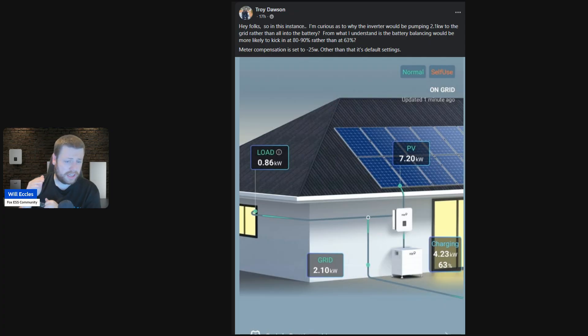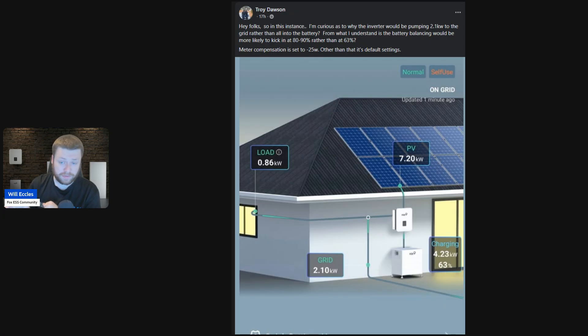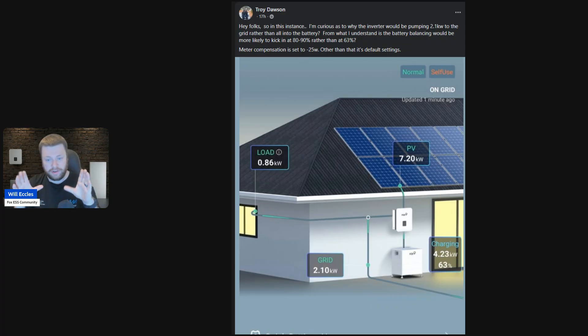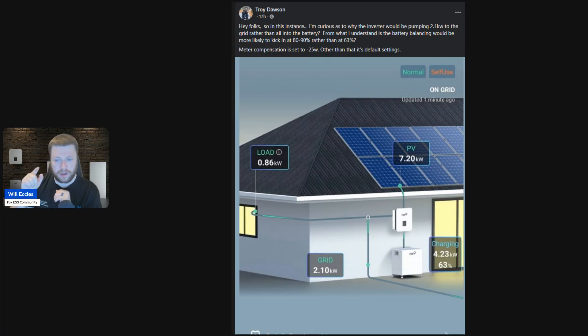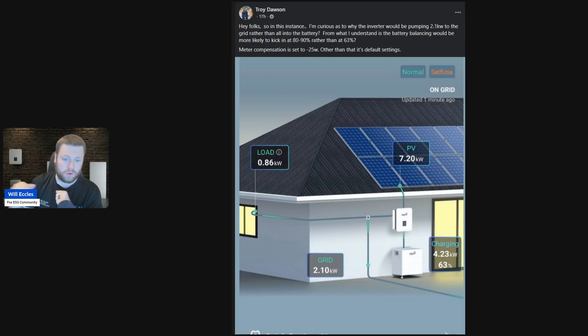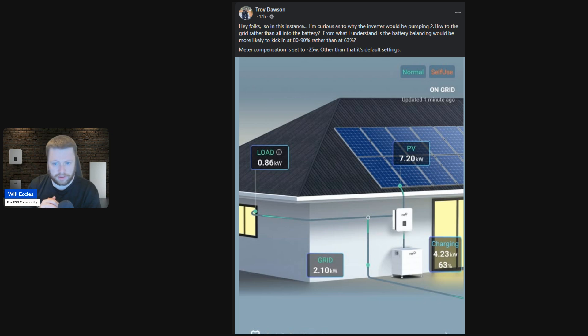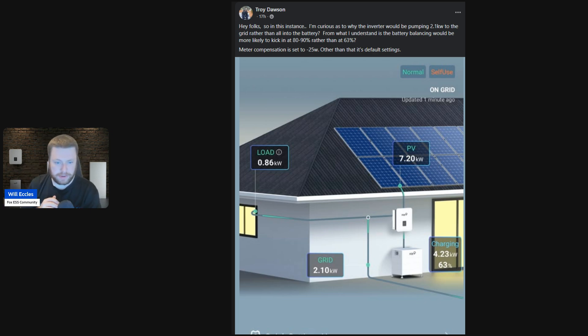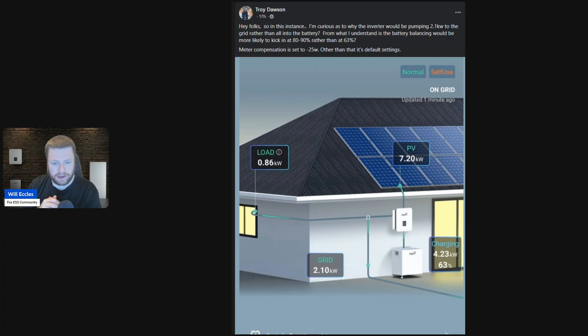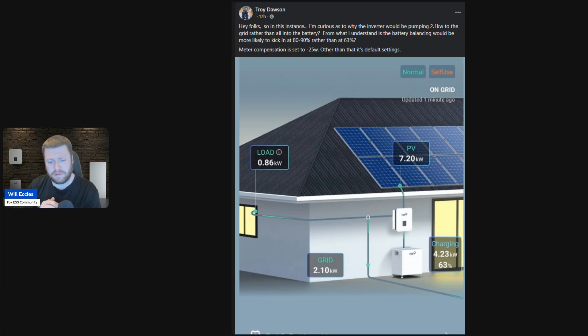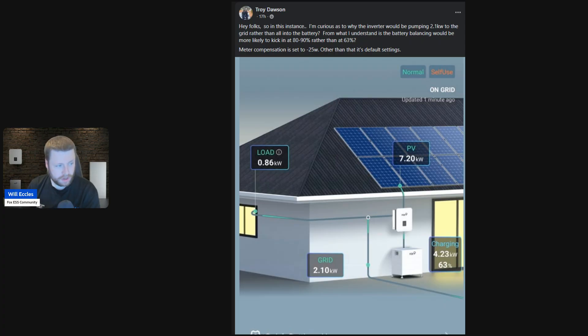Remember that the inverter can charge the batteries. If it's a DC coupled inverter, so the solar panels and the battery are plugged into the same inverter, then you can charge the batteries DC to DC from the panels and you can also export to the grid. So you don't—if your inverter is a five kilowatt inverter, you could potentially put seven kilowatts worth of panels on that. You could be exporting at five kilowatts but also charging the batteries at a couple kilowatts easily. They typically allow around 150 percent overage, sometimes it's even more than that, especially on the bigger H3 and the H3 pluses. So yeah, know that the system will always try to maximize the battery charging within the configuration, the parameters, especially in self-use mode.